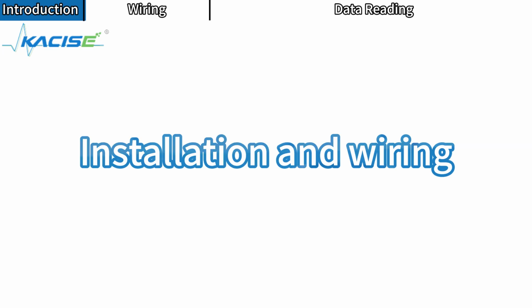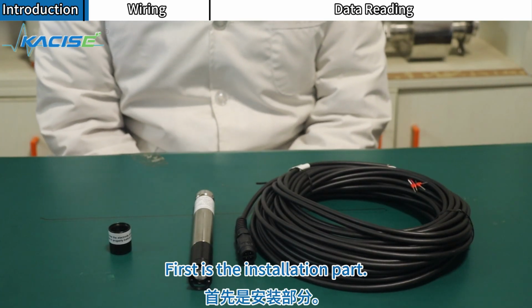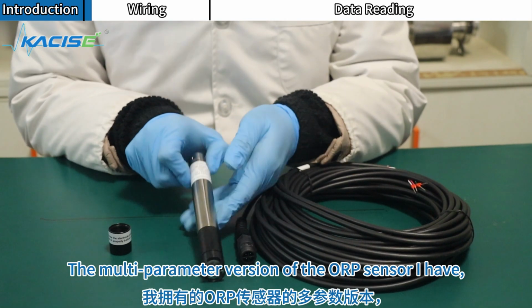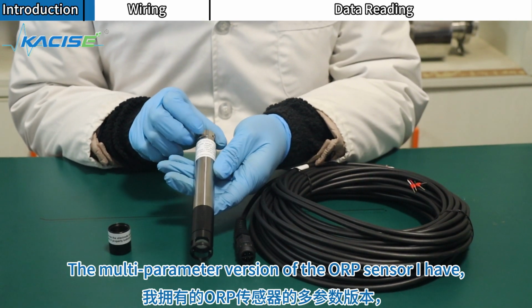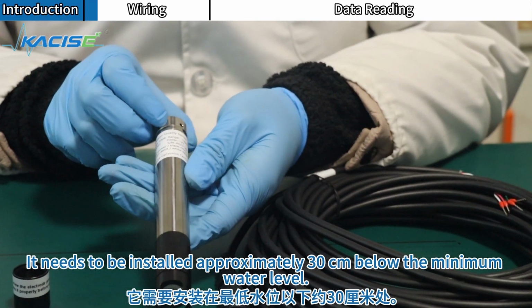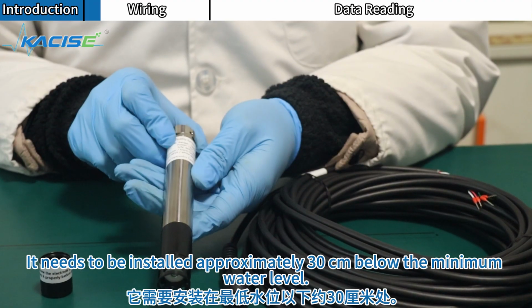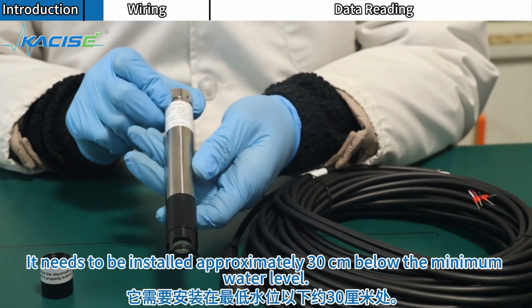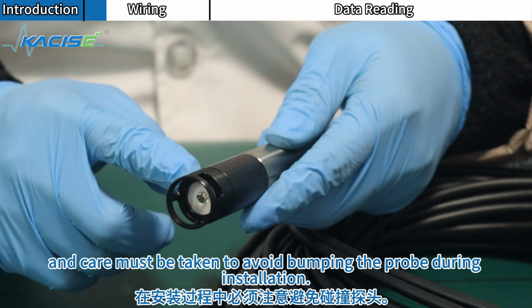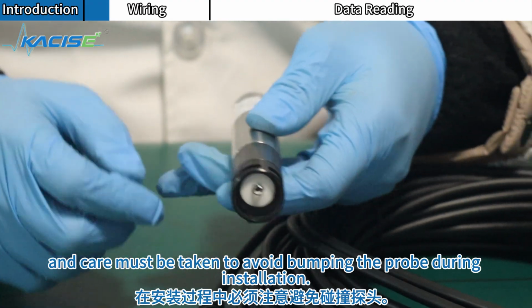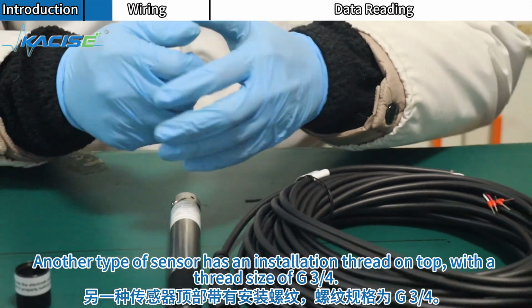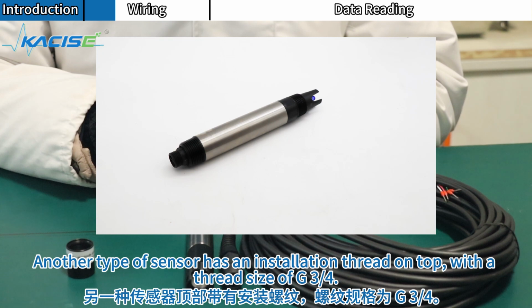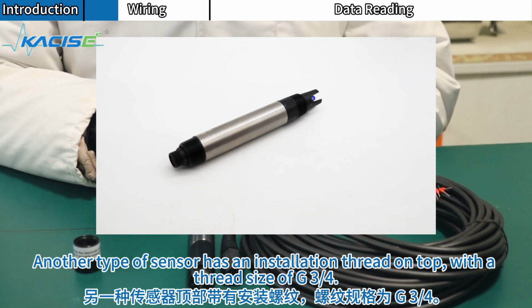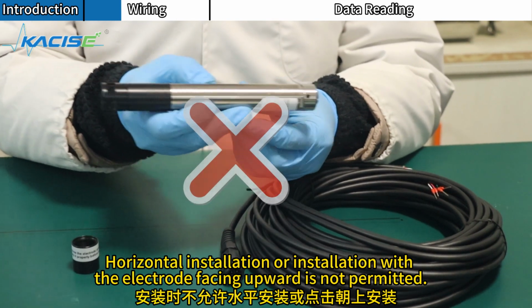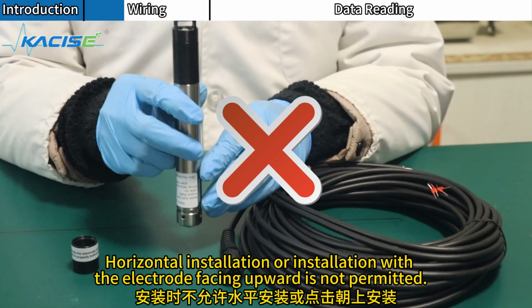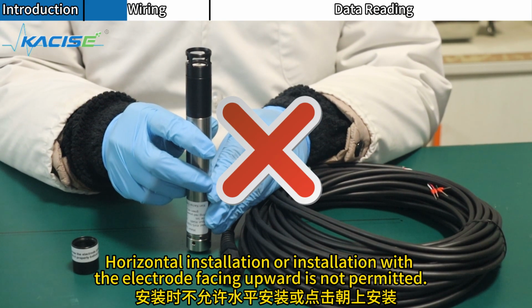Installation and wiring. First is the installation part. The multi-parameter version of the ORP sensor needs to be installed approximately 30 centimeters below the minimum water level, and care must be taken to avoid bumping the probe during installation. Another type of sensor has an installation thread on top, with a thread size of G3/4. But horizontal installation, or installing the electrode facing upward, is not allowed.